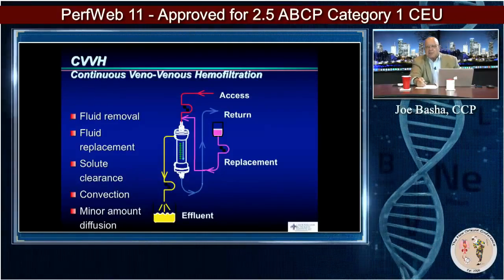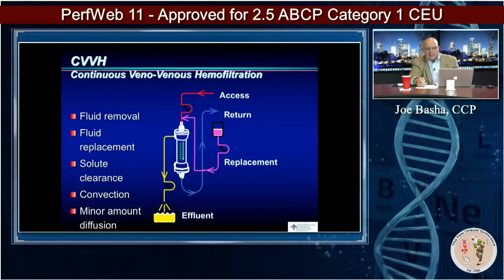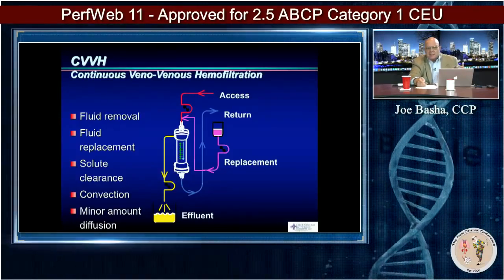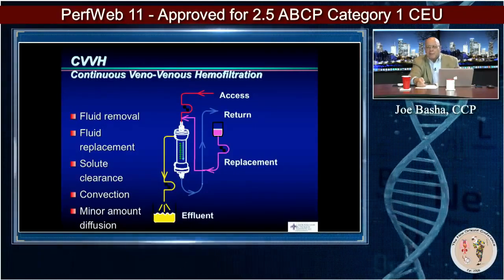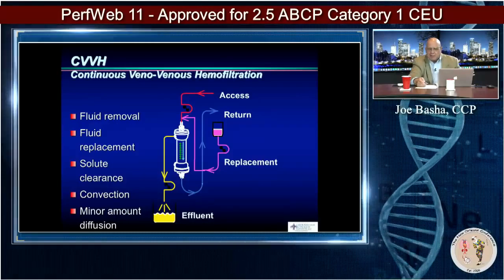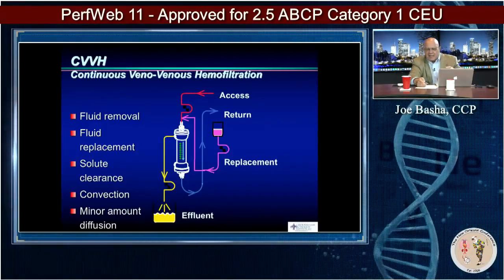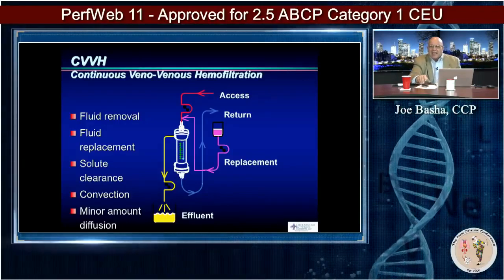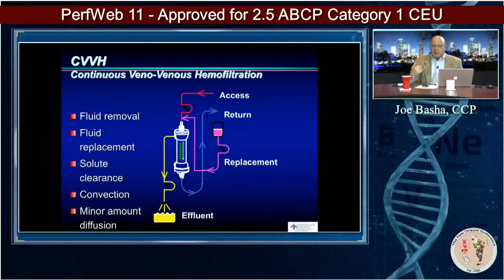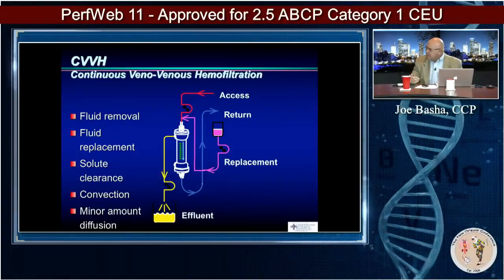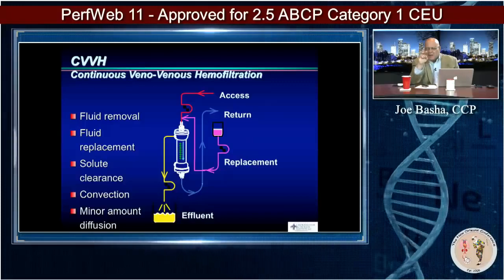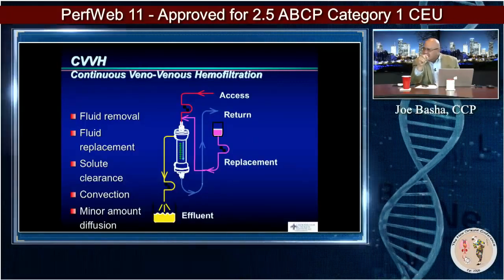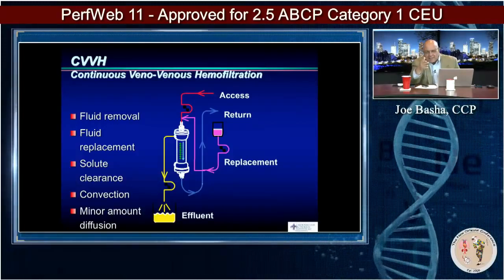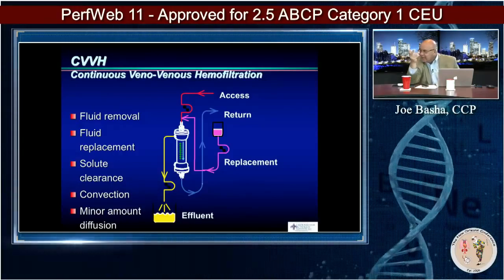So when you look at CVVH, which is my personal favorite therapeutic modality, it is used for fluid removal, fluid replacement, solute clearance, convective clearance, and a minor amount of diffusion. So you see the difference there, a very minor amount of diffusion. You see the red access coming in and then the blue going back out to the return. And this is something else. In the perfusion world, red is always return. In the dialysis world, it's opposite. Access is red, as opposed to, in our world, red being return. So keep that in mind. When you're looking at a dialysis catheter, the red is the access, the blue is the return. And that's because it's been concentrated, and that's how they distinguish those colors. But it's exactly opposite of what we're used to.